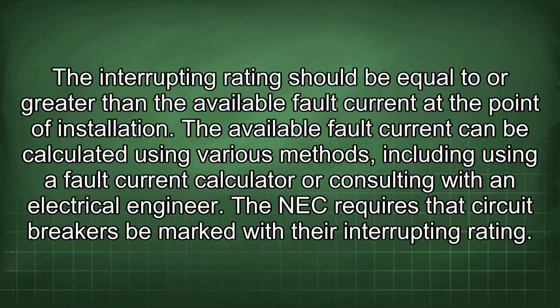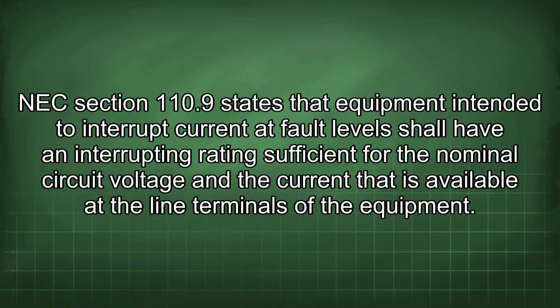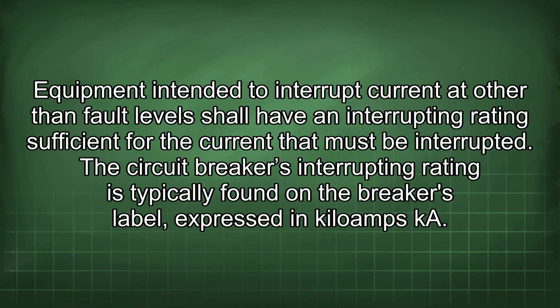The available fault current can be calculated using various methods, including using a fault current calculator or consulting with an electrical engineer. The NEC requires that circuit breakers be marked with their interrupting rating. NEC Section 110.9 states that equipment intended to interrupt current at fault levels shall have an interrupting rating sufficient for the nominal circuit voltage and the current that is available at the line terminals of the equipment.